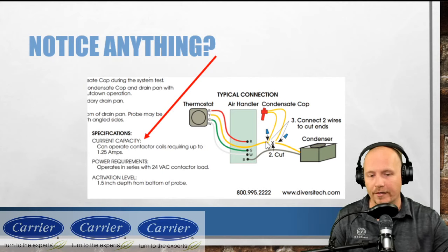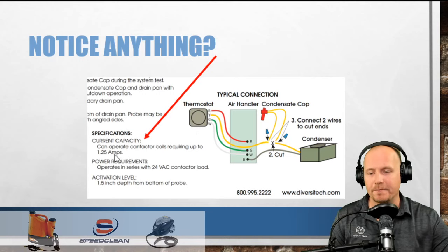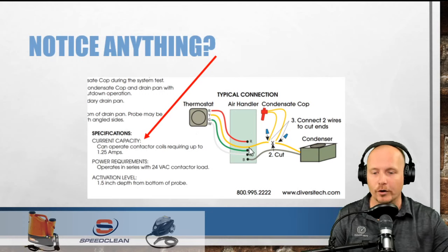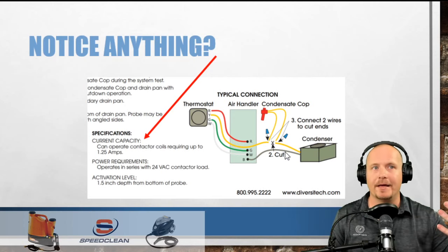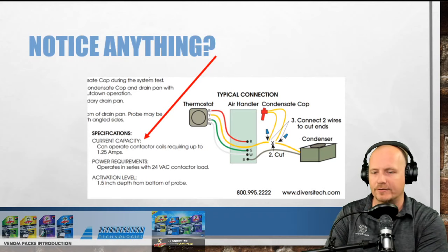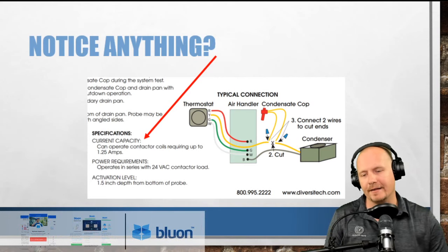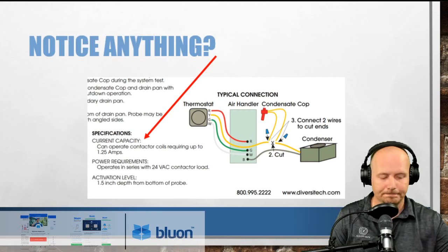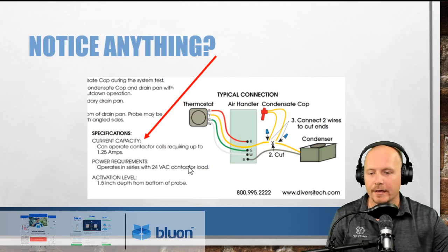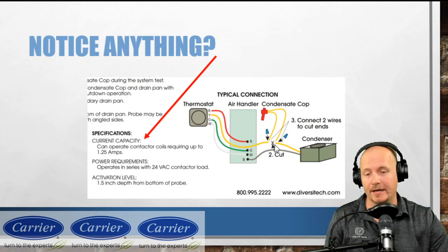And you'll see some that are a little more than that. Actually, I don't know of any that are a little less, but you will see some that are rated for a little bit more. But that's an interesting thing that we've got on float switches, which makes me think that this is an application where you would want to only break Y. If you have a system where, for whatever reason, you're running some accessories on it, which generally you should run a secondary transformer for, then depending on everything you've got going on in the low voltage secondary side of that transformer, you may need to look at either putting another secondary transformer in or only breaking Y in those particular applications, because the result is such a disastrous one.